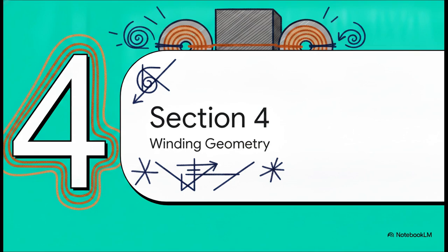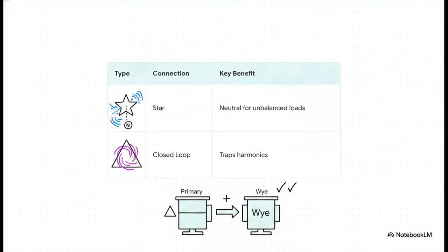And finally, Section 4, Winding Geometry. Let's wrap some copper around that iron core and look at the secret geometry of how these windings behave. Windings generally come in two main flavors. You've got Y, which is shaped like a star, and delta, which is a closed triangle loop. Y is fantastic because it provides a neutral point, which is totally essential for handling unbalanced loads in a facility. Delta, on the other hand, is great because it traps harmonic distortions inside that loop before they can leak back out onto the utility grid. And the cool part? By pairing them together, like say a delta primary and a Y secondary, you very cleverly get the benefits of both.